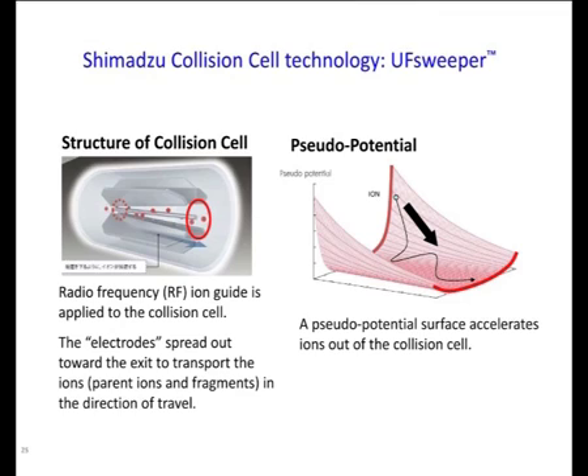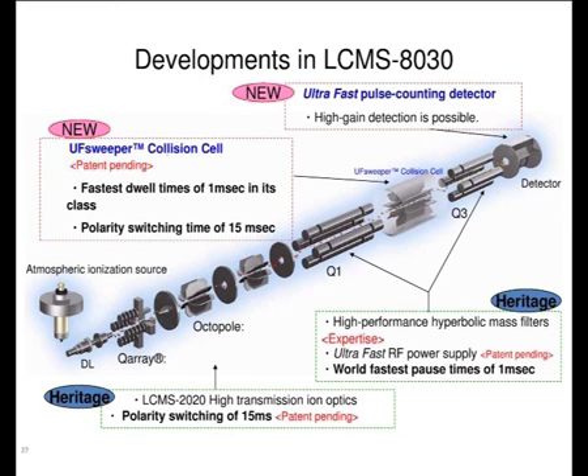To avoid that, we have provided this technique, known as the UF sweeper. In the UF sweeper, there is this type of alignment of the collision cell. It provides a pseudo potential. Generally, when the ions get fragmented in the second quadrupole, they move slowly and follow a longer pathway. But when you apply the pseudo potential, the ions sweep very easily out of the second quadrupole. You will not get the crosstalk effect. This technique is very helpful to reduce the crosstalk effect when you deal with multiple MRM events.